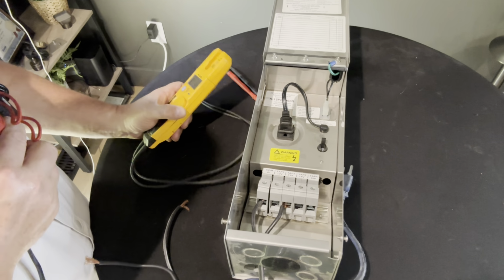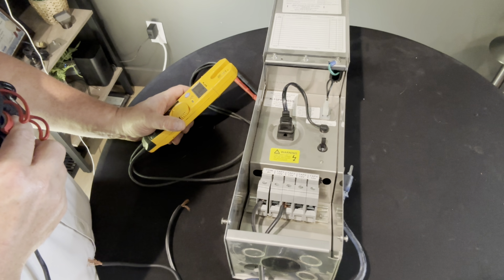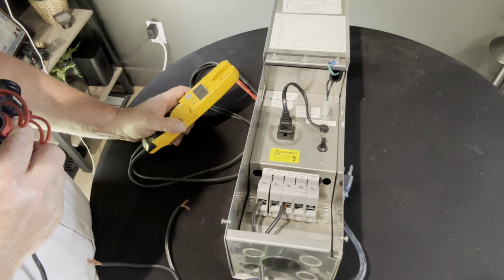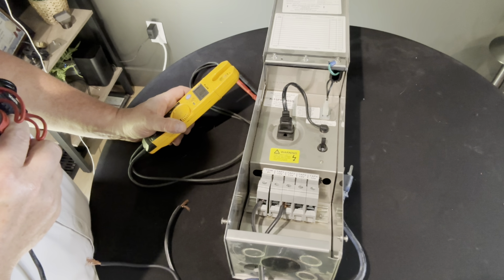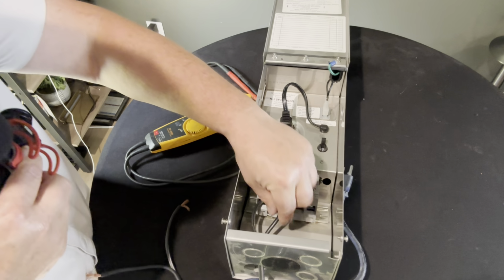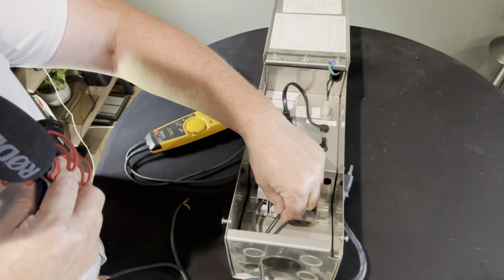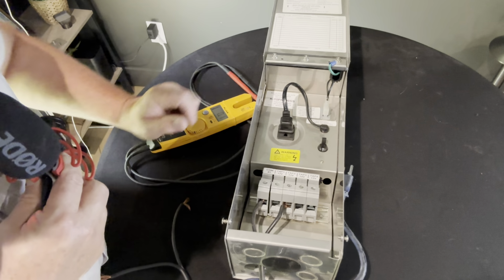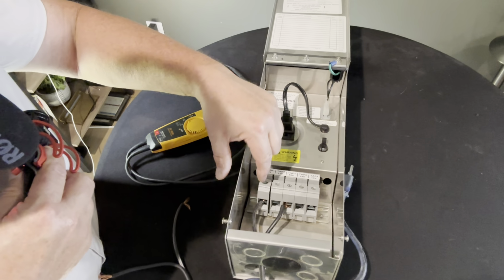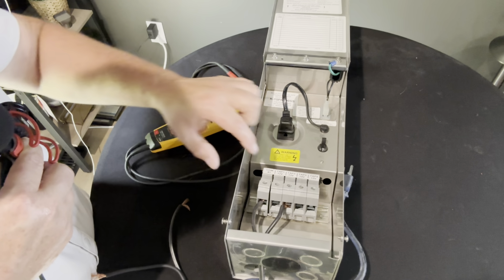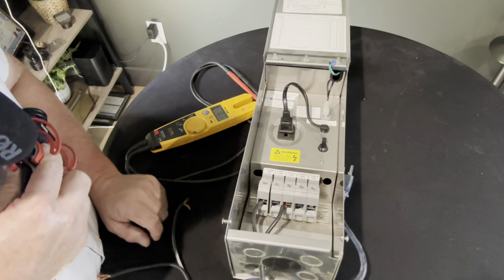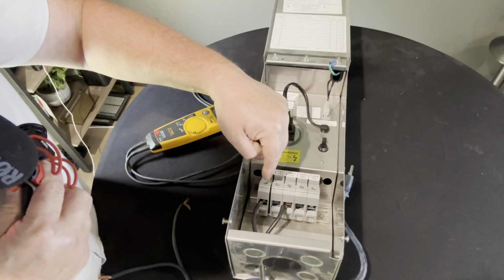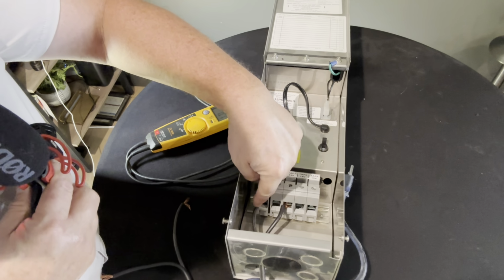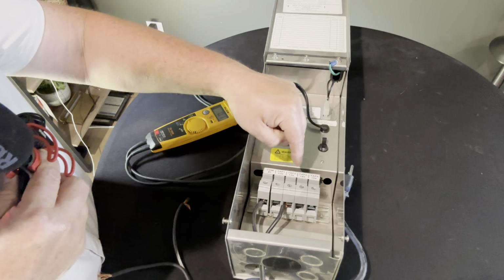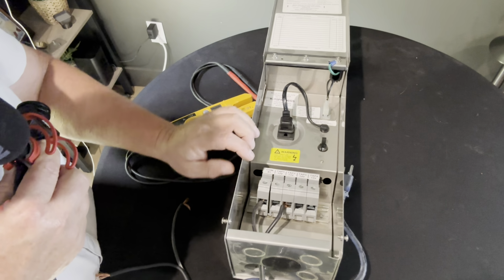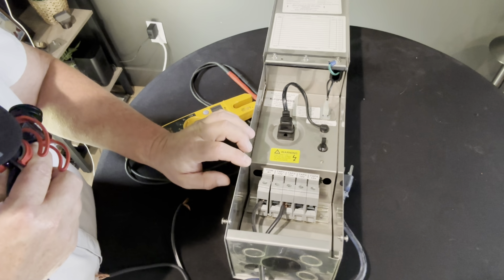The next thing you want to measure is the amps on the secondary side, so you know you're not exceeding or hurting the transformer. Now I only have one wire in here, but you can use multiple wires. If I needed to put three wires in here, I'd have two additional ones coming right into that same spot. Just because one of these spaces is taken up doesn't mean you can't use more wire.